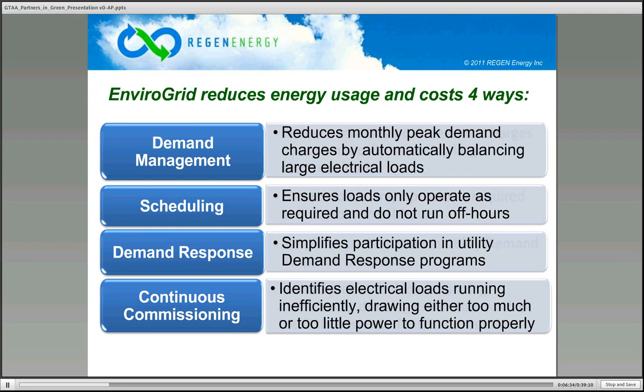Also, if a unit is drawing too little electricity, you wouldn't discover this through an alert, but looking back over the month, you might find that something you expected to kick in on a hot day to the third or fourth stage only kicked in at the first stage. That tells you there's something wrong and the unit needs to be serviced.